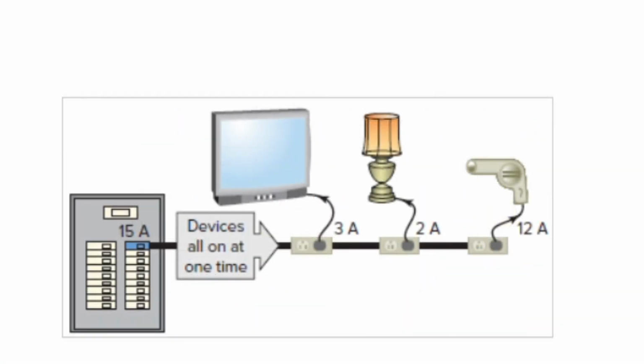An overload circumstance may also result in an overcurrent problem. Think about a scenario where too many loads are connected to a single power supply, for instance. Even with each of these loads drawing its typical amount of current, the total current may still be greater than the source's rated value. A transient overload results in a modest temperature increase and little to no impact on the equipment or conductors. But persistent overloads must be avoided because they might be harmful.